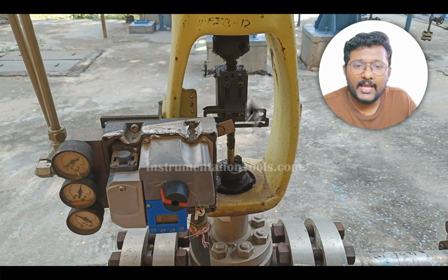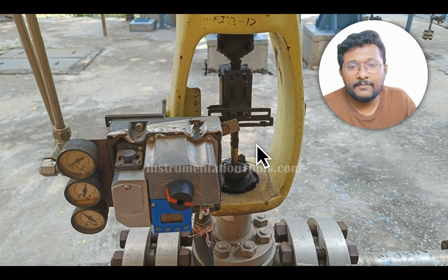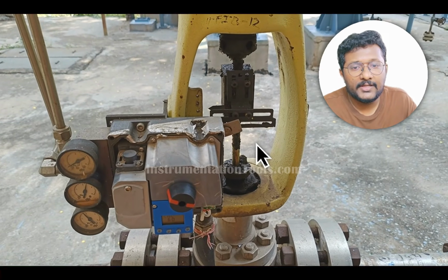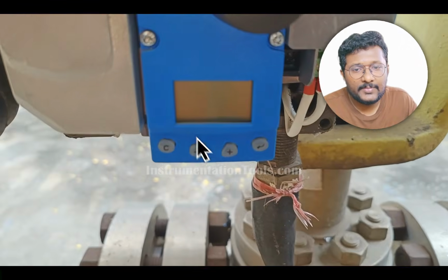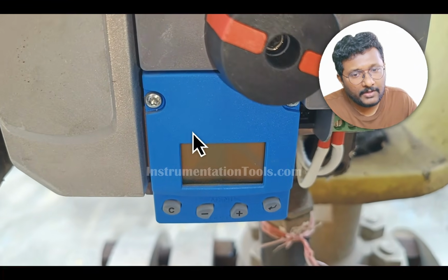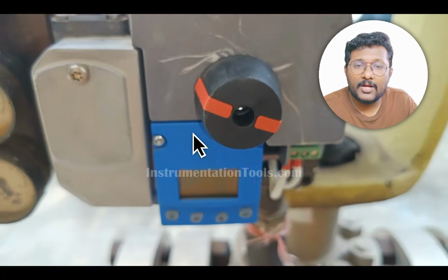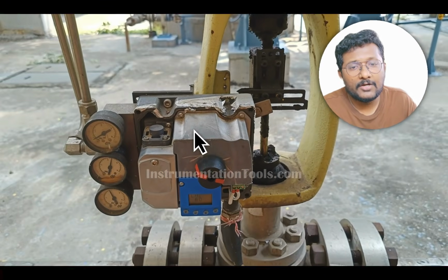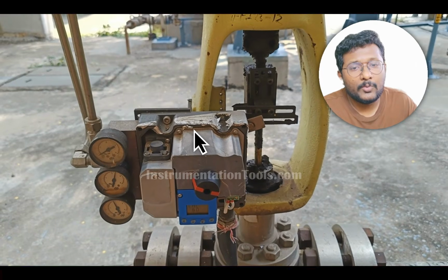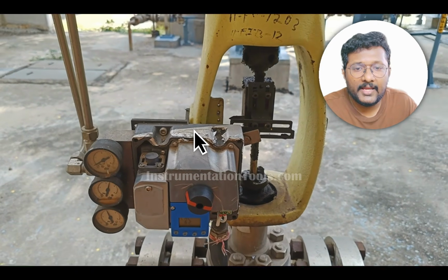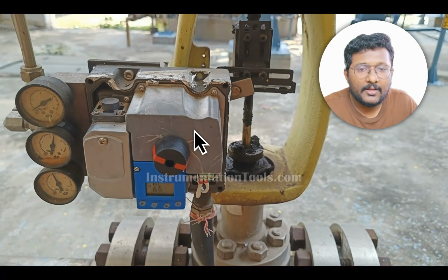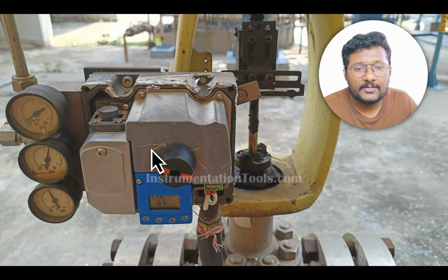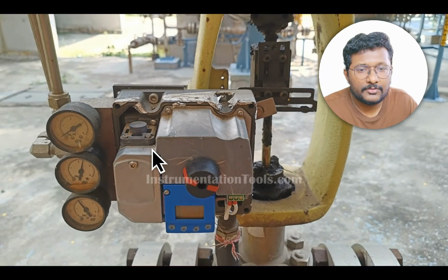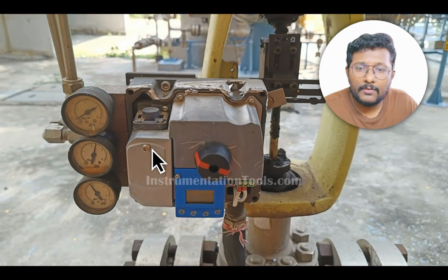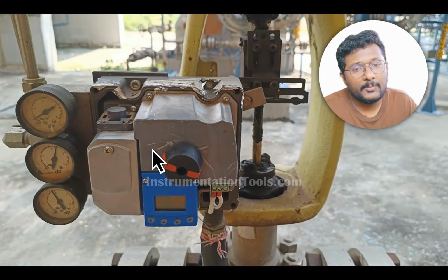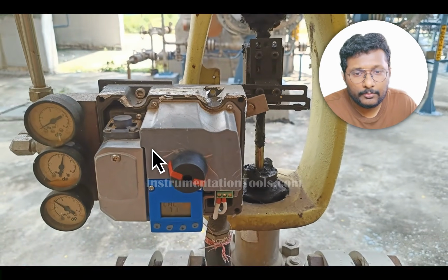Remember, you can do this calibration from 3 locations in foundation fieldbus. The first one is valve positioner display. I'm talking with respect to control valves. The second one using your HART communicator. The third one using your remote computer. If you have a valid license and hardware, you can perform these actions from your remote computer also. You can give a control valve calibration command from your remote computer in your control room.